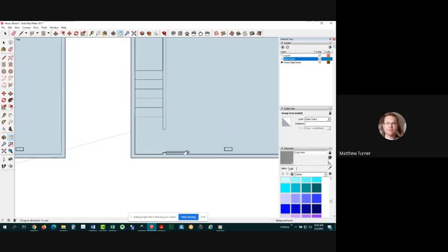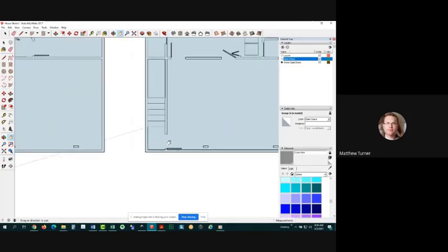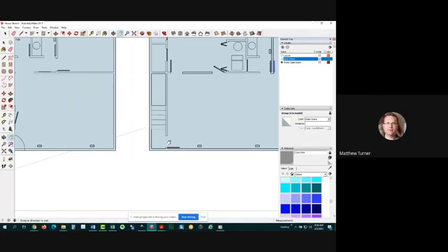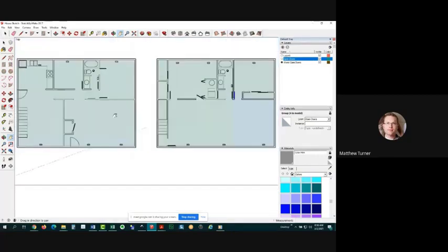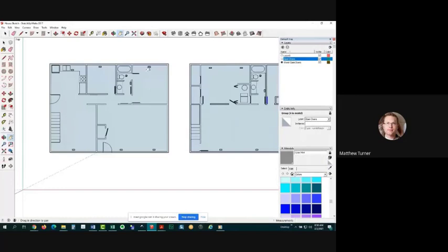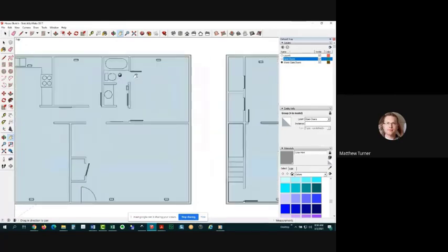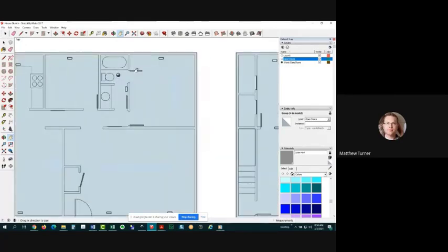And down here at the bottom of the stairs, this is what we would consider a central partitioning door. There was that door at the bottom of the stairs. When you're going through and setting up all of your doors, you go into each room and you say, okay, if this room has a supply register in it and no central returns and no fans, then I'm going to close that door. So in this case, we closed this door and we closed this door on this bedroom because it only had a supply.